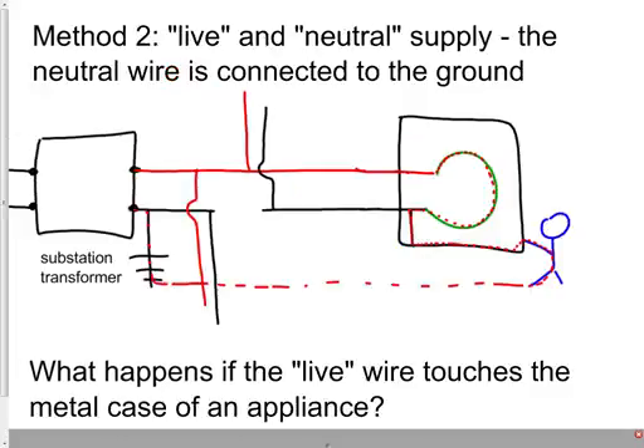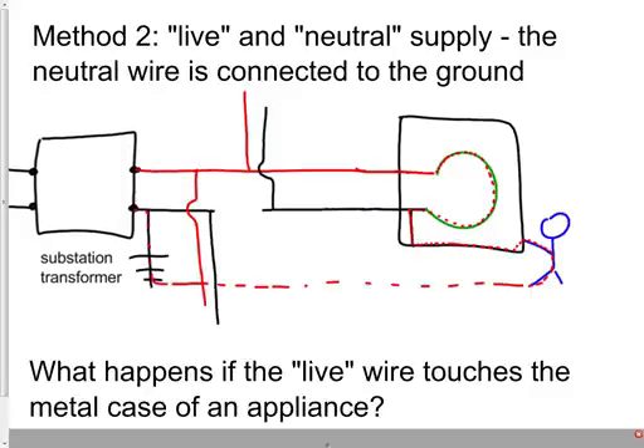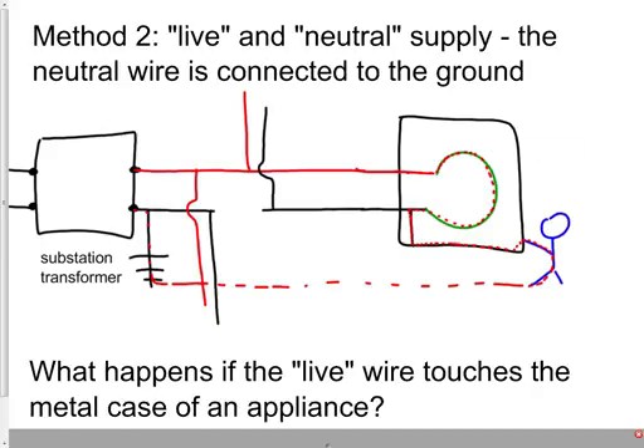Actually, some countries use this exact method 3, but other countries use a sort of hybrid between method 2 and method 3, where the earth is provided by the neutral wire, but it branches off inside the house into a separate circuit to reduce the risk of the neutral becoming disconnected.